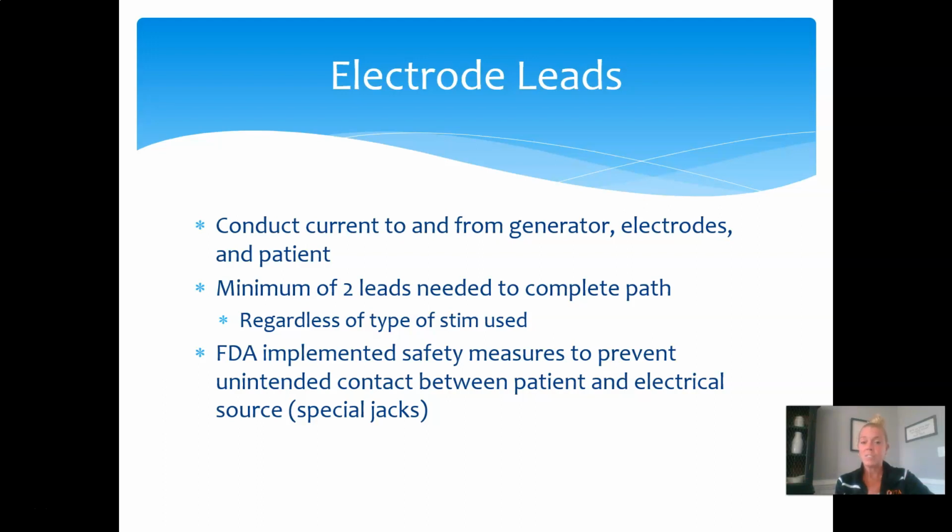There are special safety measures that are built into all of the machines that are protective, right, for the patient and for you, to make sure that we're not getting any unintended contact with electricity. Most will have a special plug. The plugs with the 3 prongs, that helps to ground that. So again, we're not getting any unintentional electricity delivered from the wall.